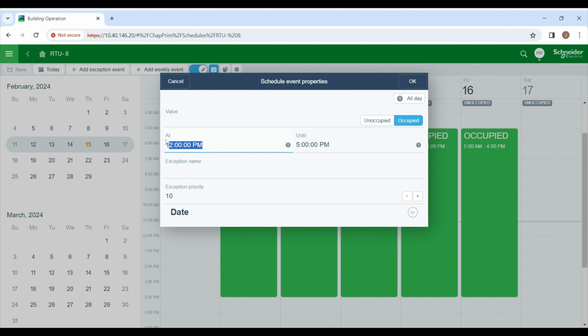you can specify the time. So your schedule is from 4 a.m. to 4 p.m., and he tells you, I want this equipment to run up to 7 that night. You know it's ending at 4, so you have to have an extension time after 4. As we talked about the other day, if your schedule is ending at 4, don't start your event at 4, because the equipment might shut down and turn on again.